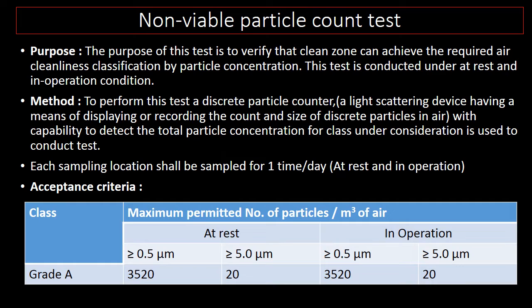The acceptance criteria for this test specifies the maximum permitted number of particles per meter cube of air. For Grade A, at-rest condition: 0.5 micron particles shall not exceed 3520 and 5 micron particles shall not exceed 20. For in-operation condition, the same limits are applicable — 0.5 micron particles shall not exceed 3520 and 5 micron particles shall not exceed 20.